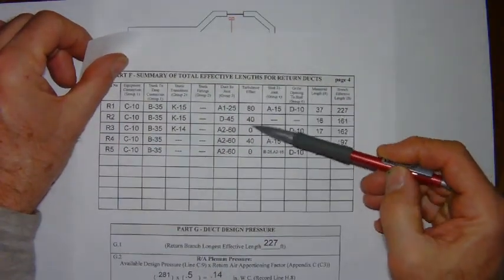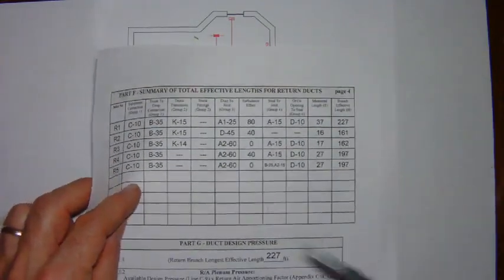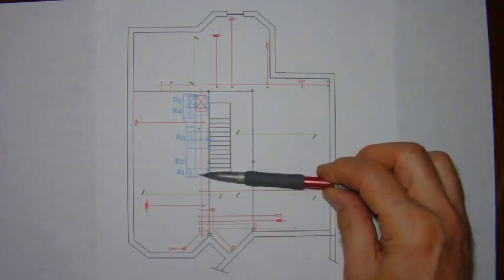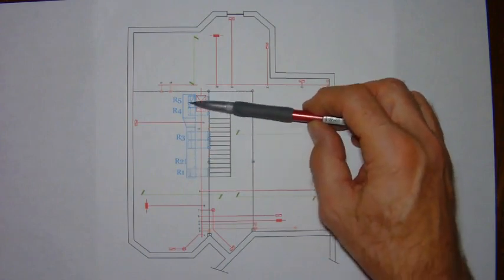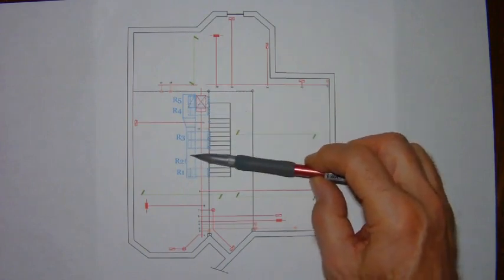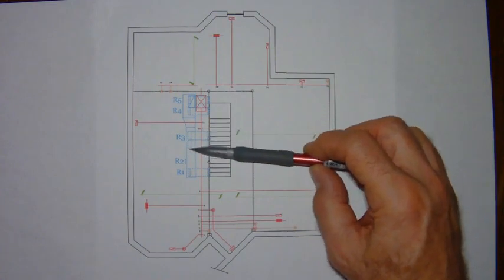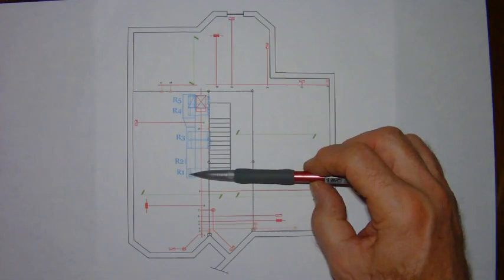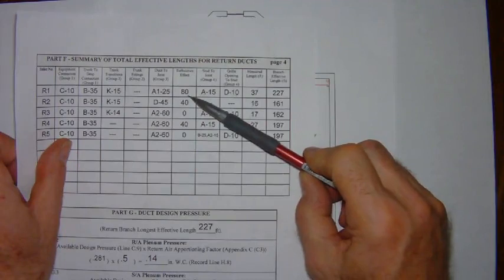We've got the turbulence effect. If you recall that deals with the intersection of the different return airs. So the air from R1 enters the duct here, and as it's flowing back towards the furnace, it has to intersect with R2. So there's the first intersection point. As the air continues, it intersects with R3. So for R1 we have 40 and 40, so that makes 80 feet of turbulence.